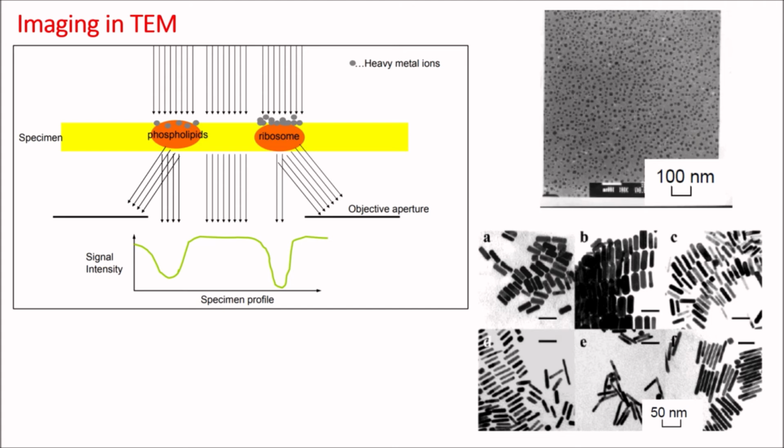Electron microscopy is usually performed in the dark to receive a good contrast on the viewing screen. For many decades, images were taken by exposing electron-sensitive films to the electron beam, and the negatives were developed by conventional film development in a dark room. Nowadays, specialized CCD cameras are used for image acquisition. CCD cameras are available which reach the resolution of a conventional chemical film.